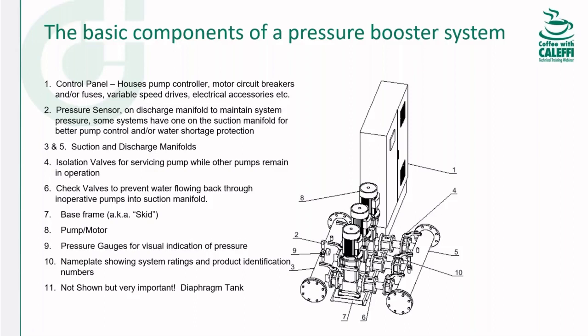Pressure gauges, that's pretty easy stuff, right? But please, to everyone out there, make sure that you require and/or install for your contractors a pressure gauge on the suction side of any pump or any booster, because the first step of troubleshooting is let's check the inlet pressure and the outlet pressure, get our differential pressure, and compare that to the shutoff head on the pump curve. If we don't have a pressure gauge on the inlet, we can't do that, and you can't really troubleshoot a pump very efficiently.